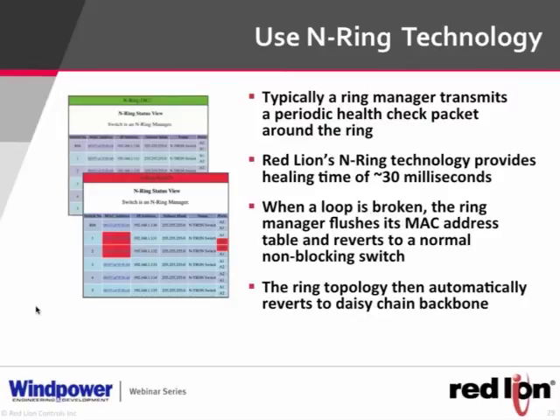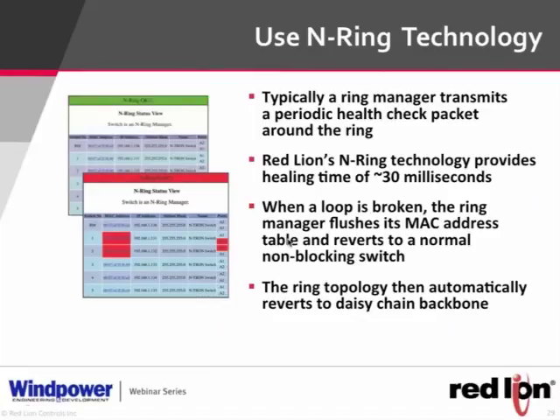The ring manager sends a health packet around the ring continuously. If it fails, the manager retries a couple of times, then at 30 milliseconds triggers healing. N-Ring also provides reporting features absent from RSTP and most ring protocols: it tells you exactly which switch and which port experienced the failure. If someone cuts a fiber cable, you don't have to log into every switch to find it — N-Ring pinpoints it. If the ring breaks, traffic continues in a chain topology until the fiber is repaired.